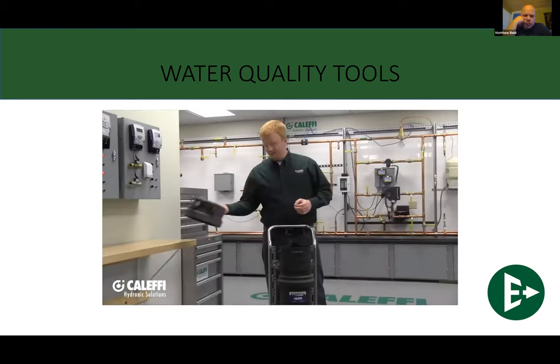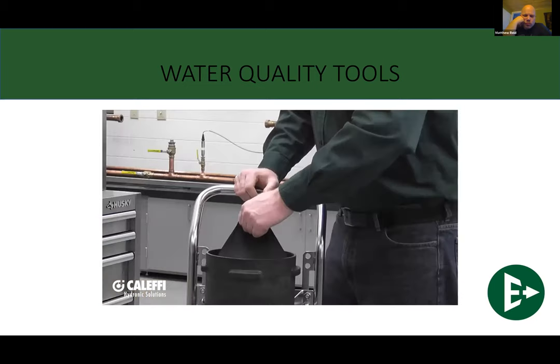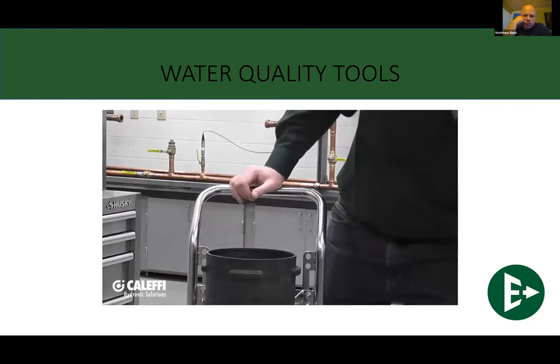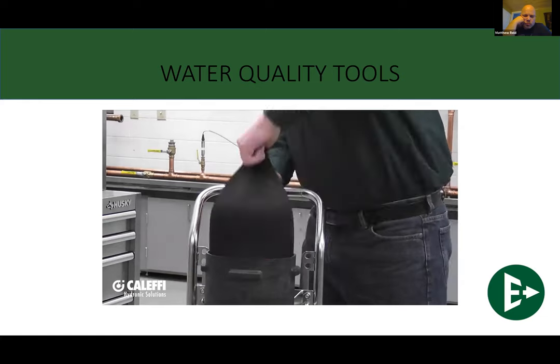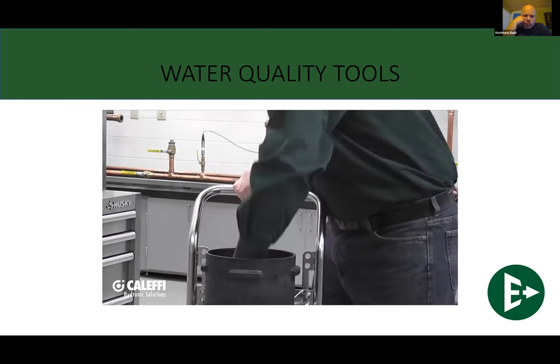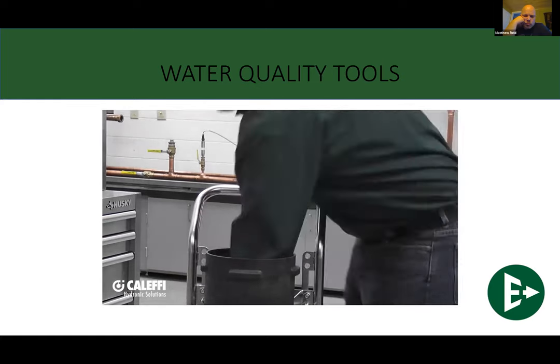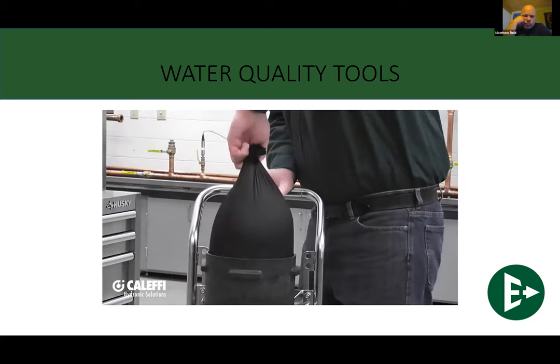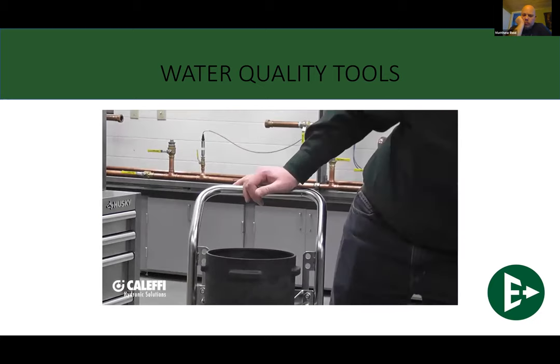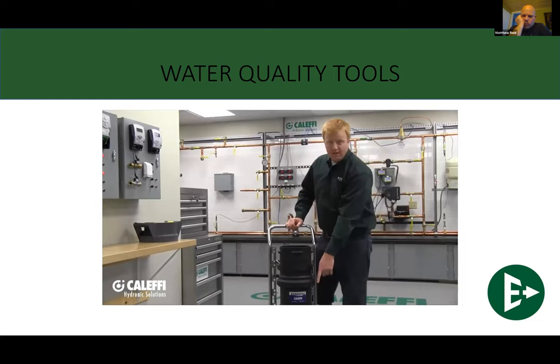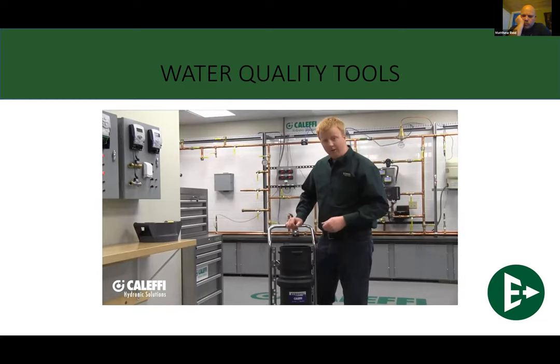Removal of the resin bags is pretty straightforward. You're just going to grab a hold of the top of them and pull them out and set them aside here. We do offer replacement resin bags for the 2 and 4 bag models. You'll also want to make sure to keep the drain valve open at the very bottom, so that if there's any suction pulling out that last bag, it'll make your life a little easier.